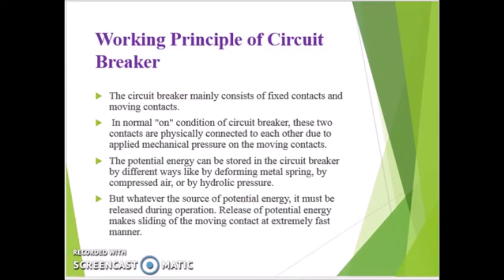In the working principle, the circuit breaker mainly consists of a fixed contact and a moving contact. In the normal on condition of the circuit breaker, these two contacts are physically connected to each other due to applied mechanical pressure on the moving contact. The potential energy can be stored in the circuit breaker in different ways, like by deforming a metal spring, by compressed air or by hydraulic pressure.